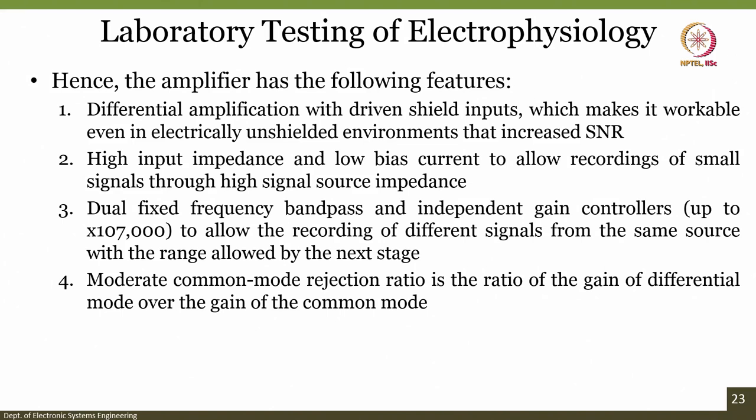The amplifier circuit used to amplify the signal should have the following features. First, differential amplification with driven shield inputs, which makes it workable even in electrically unshielded environments and increases the SNR. Second, high input impedance and low bias current to allow recordings of small signals. Third, dual fixed-frequency bandpass and independent gain controllers to allow recording of different signals from the same source. Fourth, moderate CMRR — common mode rejection ratio — which is the ratio of the differential gain to the common mode gain.